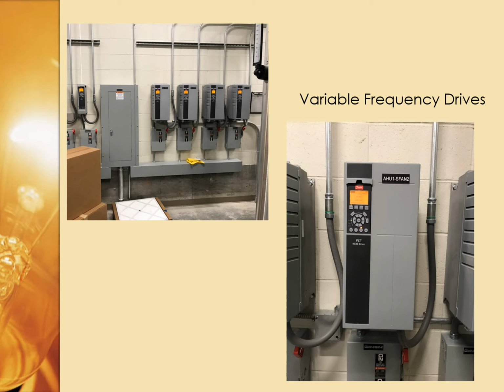There might be 30 or 40 of these things, and it literally makes a wall of fans, what they call a fan wall. The beauty of that is it's very easily controllable. You're not trying to start one gigantic motor for one gigantic fan, you're starting a whole bunch of little ones. Plus if one or two happen to fail and need maintenance, the whole system doesn't go down. It's very clever, and I wish I could show you that, but that's what these are.